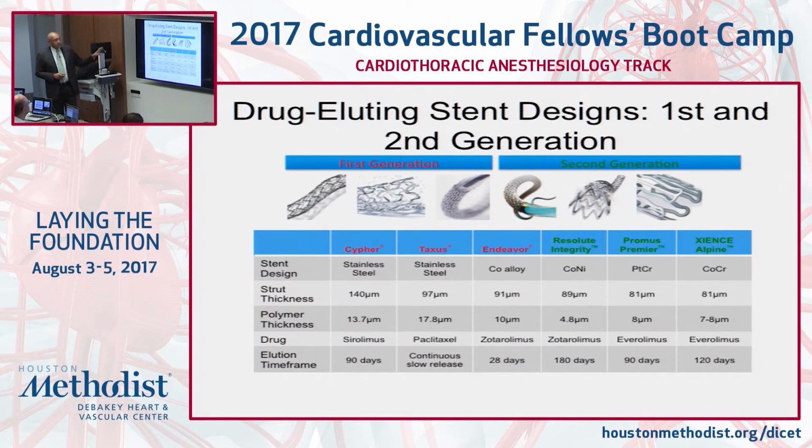I want to point out some subtle changes or advances in the stent designs and technology. This is what has allowed our field, the interventional cardiology field, to advance, this very slide. For example, we have moved away from stainless steel. So if somebody presents data on a stainless steel stent, you have to almost think twice about it now, because we have found much better alloys: cobalt nickel, platinum chromium, cobalt chromium. Strut thickness has almost halved from 140 to 150 microns. Now anything more than 80 microns is kind of scoffed at.